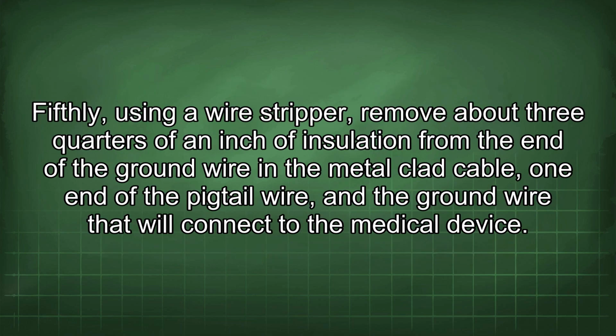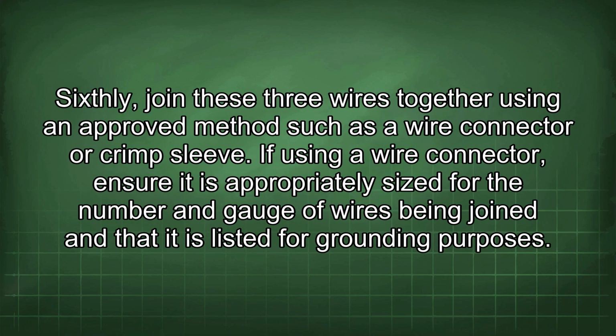Fifthly, using a wire stripper, remove about 3/4 of an inch of insulation from the end of the ground wire in the metal-clad cable, one end of the pigtail wire, and the ground wire that will connect to the medical device. Sixthly, join these 3 wires together using an approved method such as a wire connector or crimp sleeve. If using a wire connector, ensure it is appropriately sized for the number and gauge of wires being joined and that it is listed for grounding purposes.